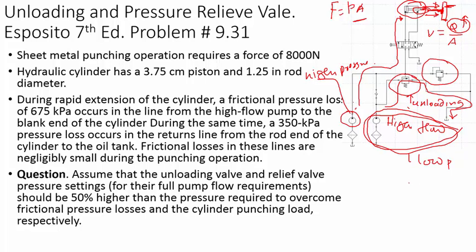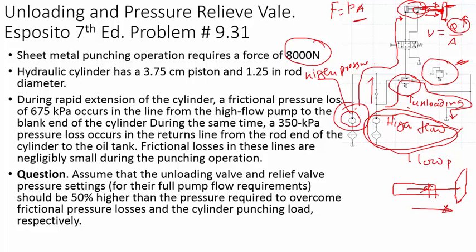When the cylinder is fully extended and the punch reaches the sheet metal, the high-pressure pump holds the pressure and maintains about 8000 Newtons of force to perform the punching operation. The question asks how to set the unloading valve pressure and the pressure relief valve pressure. When the cylinder is moving fast, there is a lot of fluid motion — friction losses on the blank side of about 675 kilopascals and on the rod end of about 350 kilopascals.